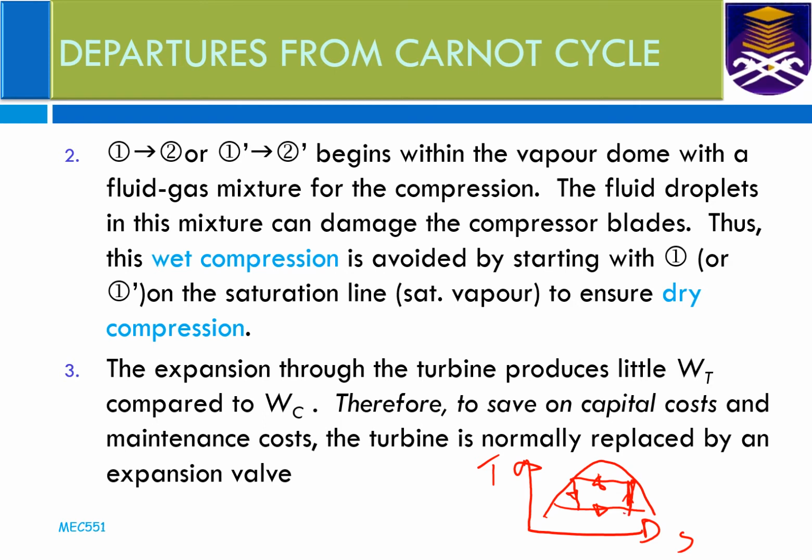For the process from 1 to 2 in the compressor, at the beginning of the compression the compressor would have to work in a multi-phase environment. Thus there will be a wet, or more correctly liquid, phase of your refrigerant. This is not a good condition for the compressor to work with.